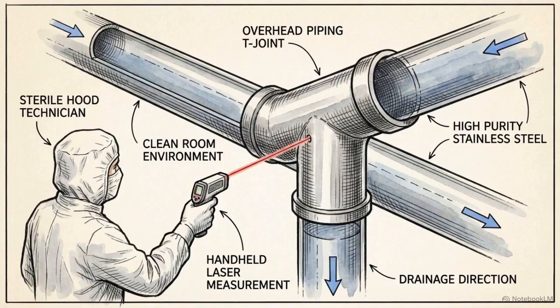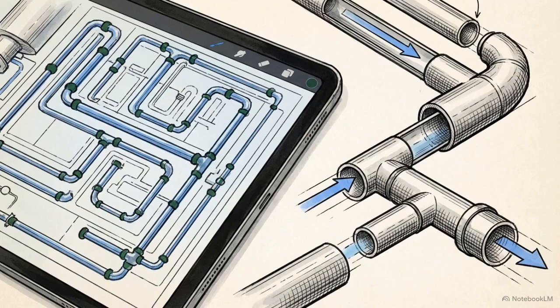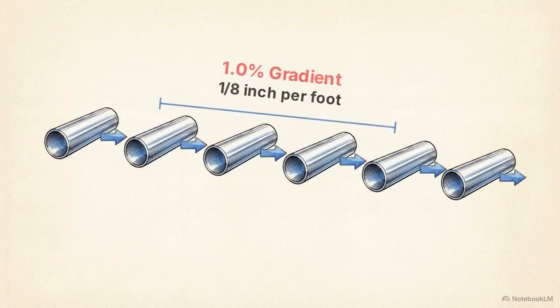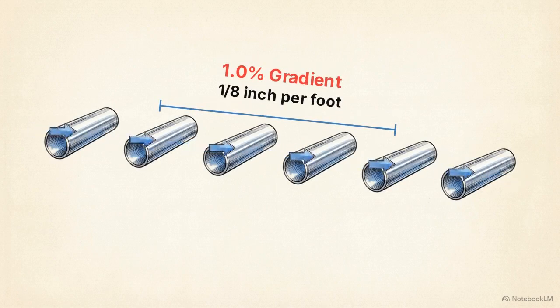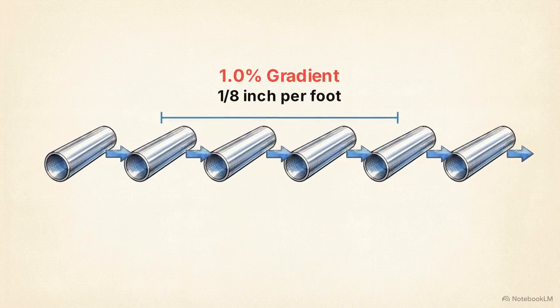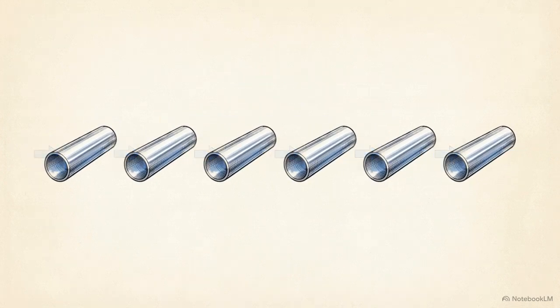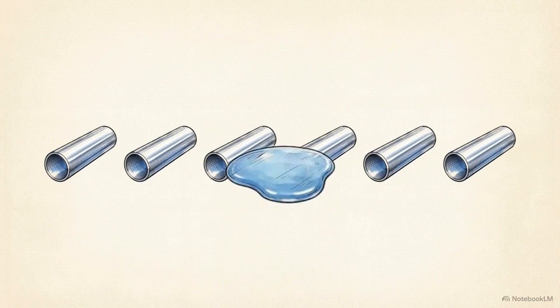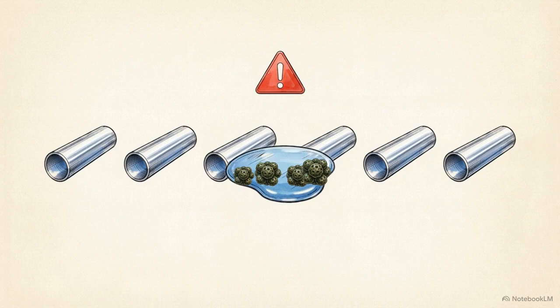The process begins with measuring the physical elevation at every weld point along the pipe run to identify potential flat spots. The ASME BPE standard defines the pitch. For every horizontal foot, the line must drop 1/8 of an inch, a continuous 1% slope. If this pitch is lost, gravity stops pulling water. The resulting puddling provides the environment bacteria need to anchor to the steel.